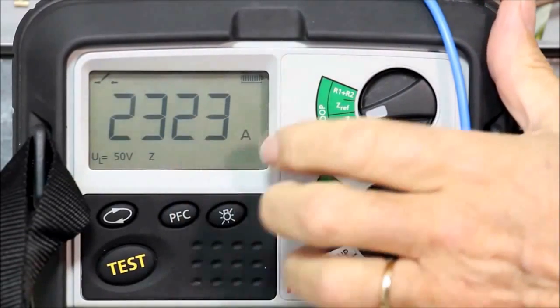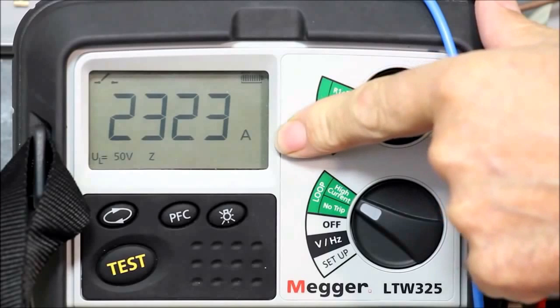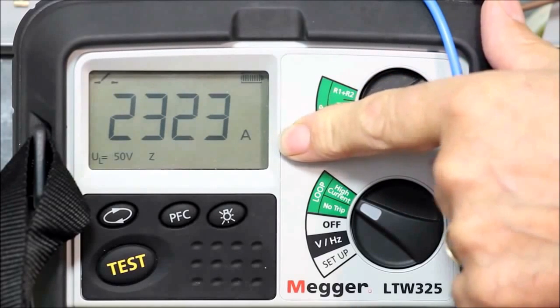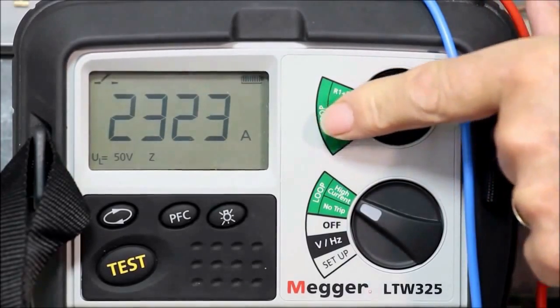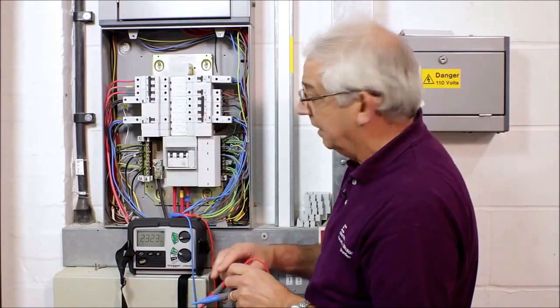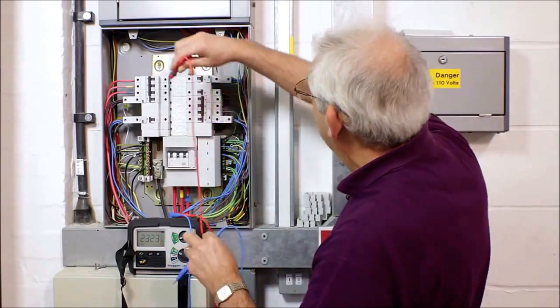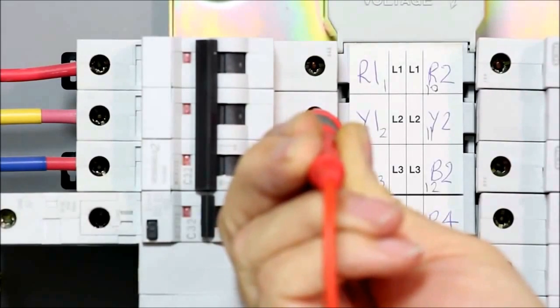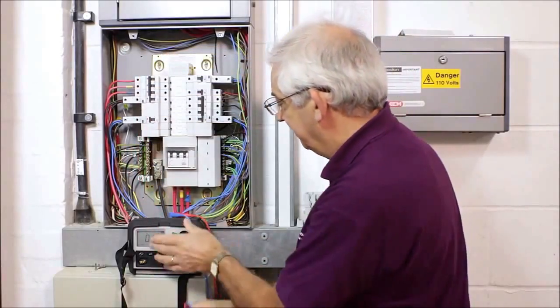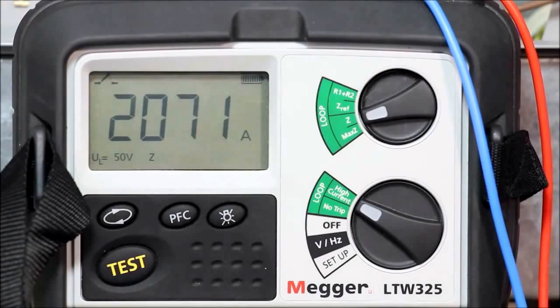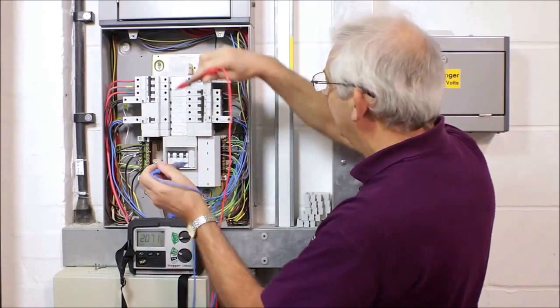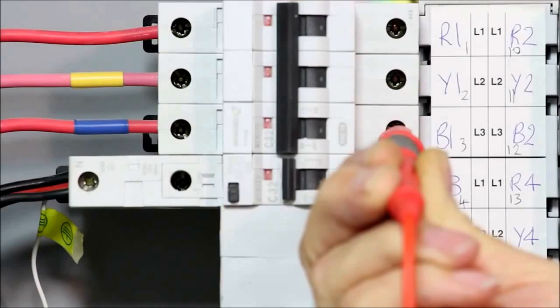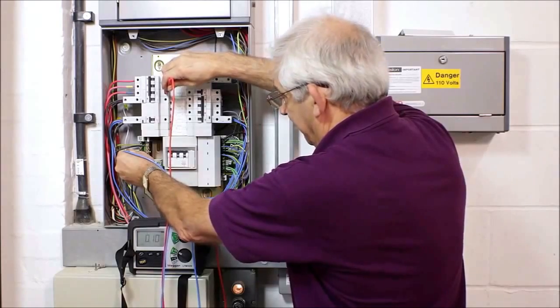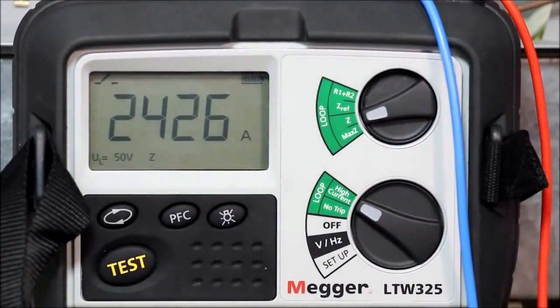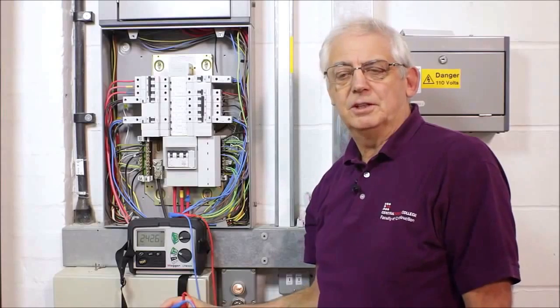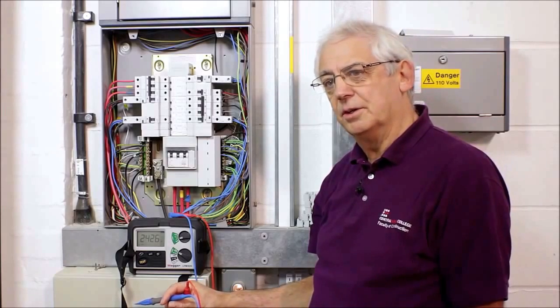And with this machine, I need to push a button to give me PFC. And we can see that the maximum current between earth and L1, or this is an old board, so the red phase would be 2,323 amps. I then can do the test between the yellow phase, which would now be known as L2. Up here, look, we can see it's indicated it's the yellow phase to earth. Take a reading, push the button, and I've got 2,071 amps, which again is very close, so that's good. Next, I go to the blue and earth, take another reading, push the button, 2,426. So roughly speaking, 2,400 amps is the highest it can flow between any line conductor and earth.